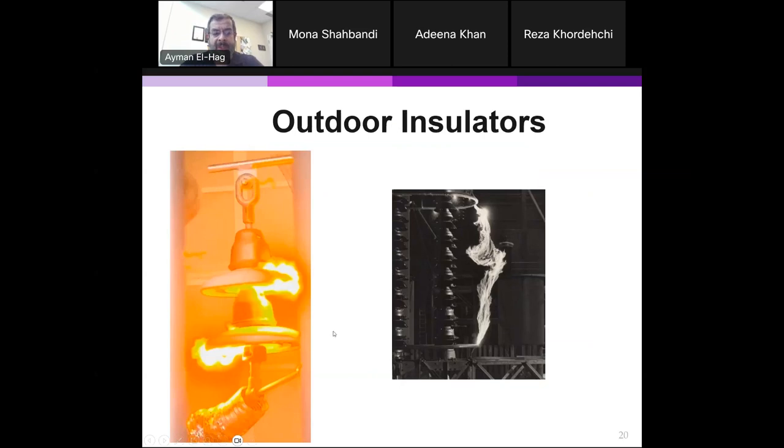Now, outdoor insulators are used basically as self-restoring insulation at the system level. For example, recently Abdullah took this in the high voltage lab. This is a two-disc insulator, while doing his research. He is trying to detect damage of ceramic insulators using ultrasonic sensors and machine learning as well. Here you have a flashover on the insulator surface. When the flashover is over, you can retake the test and it will withstand the test. Not at the same voltage level, but at the normal operating voltage it can work again, even after 2, 3, 10 flashovers, as long as you are not damaging the ceramic insulator itself. The breakdown is happening only in air, so there is no issue here at all.